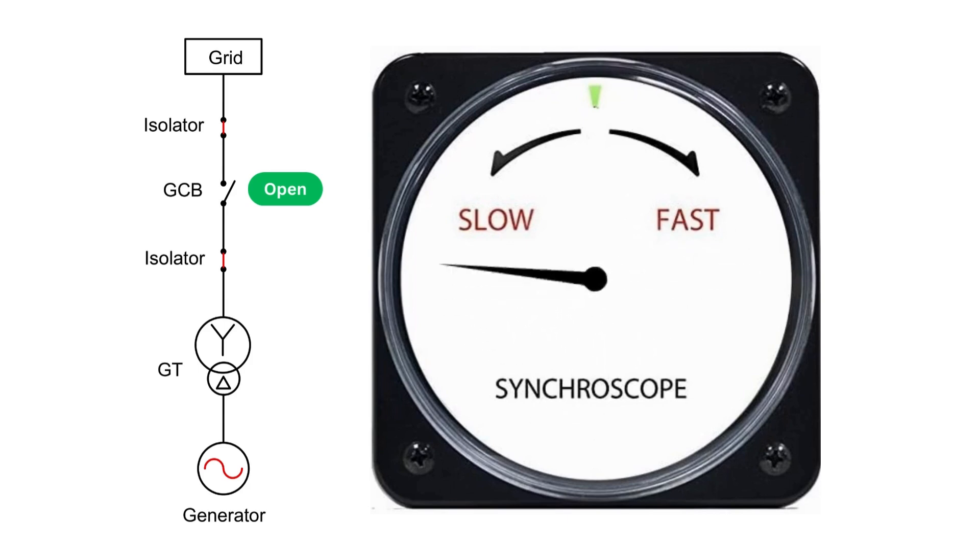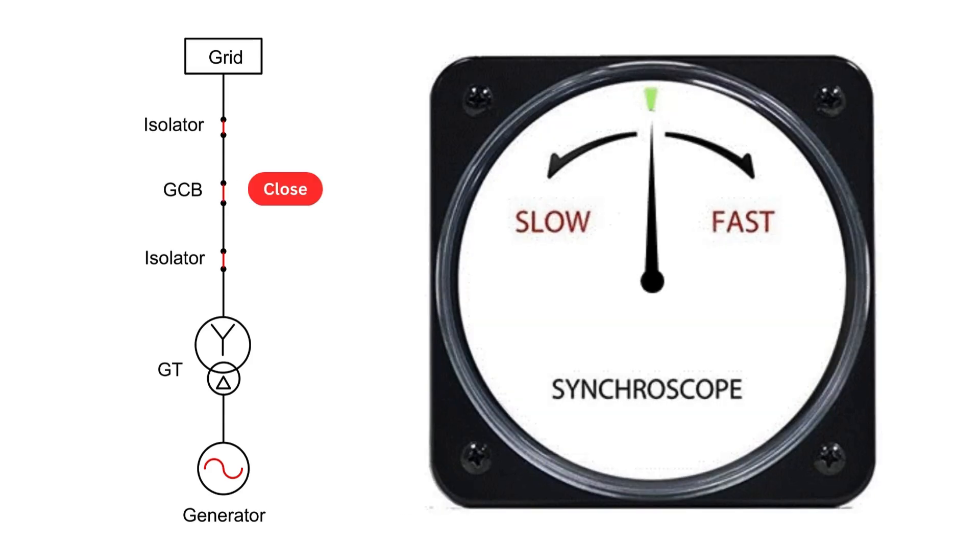In modern power plants, auto synchroscopes handle these adjustments automatically. Once parameters are matched and the synchroscope needle reaches 12 o'clock, it commands the GCB to close, connecting the generator with the grid.